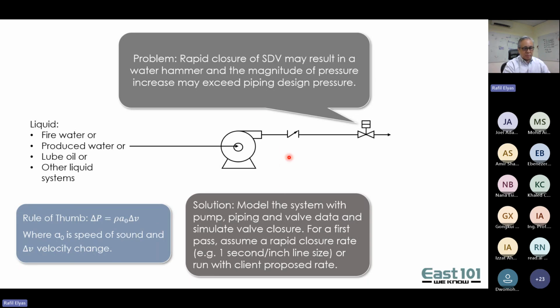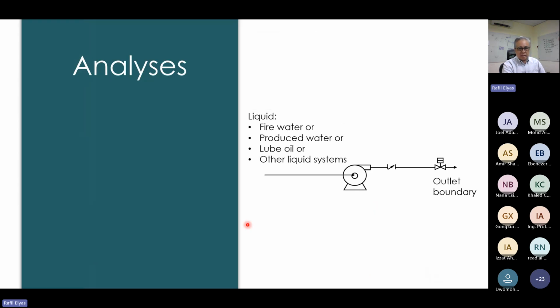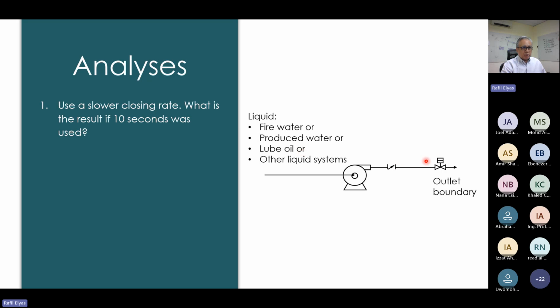So in this particular case, for something a bit more complex, we've got the pump curves, the piping configuration with isometrics, valve data, and we actually shut down the valves, open and close the control valves, do switchovers, and things like that. And we take a look at the pressure, potential pressure surges and pressure increases across the system. So in some examples, if you have a closure and you want to prevent this system from potentially surging, we take a look at what some of the limits are that we can have on the valve closure.